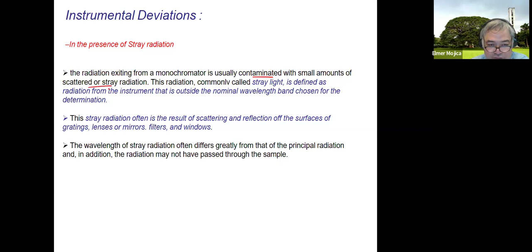And this usually results from scattering and reflection off the surfaces of gratings, lenses, mirrors, filters, and windows, or whatever optical components your instrument has. The wavelength of this stray radiation often differs greatly from that of the principal radiation, and in addition, the radiation may not have passed through the sample. That's why you call it stray radiation. So if we look at stray radiation, this is usually what's happening.